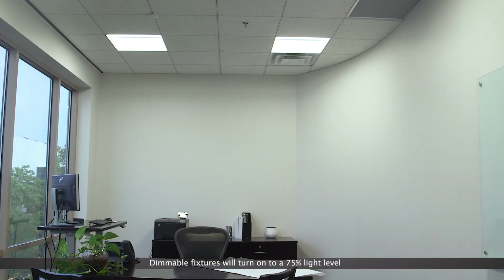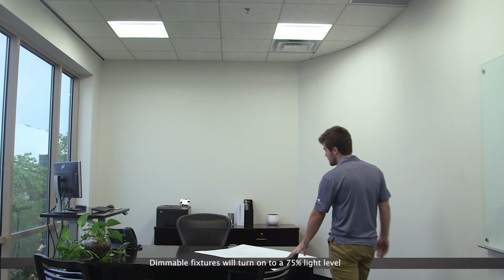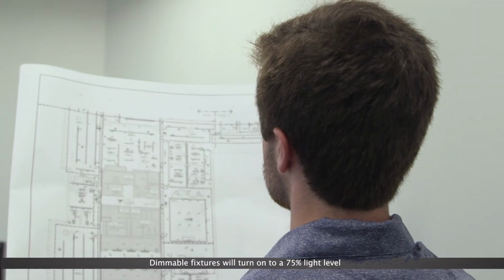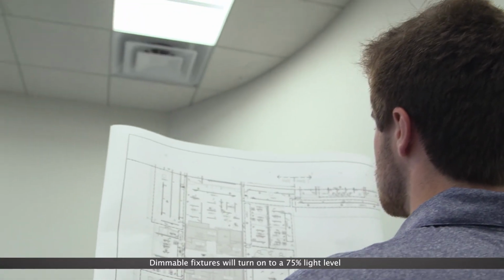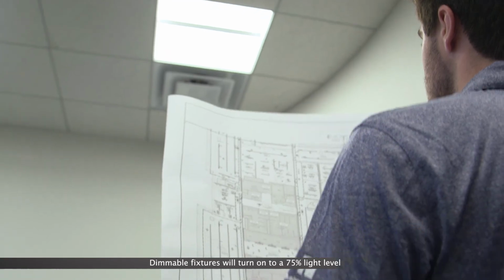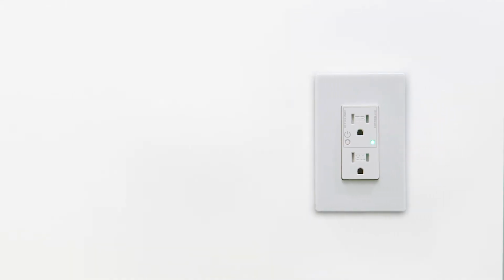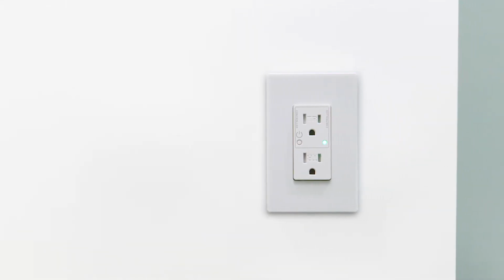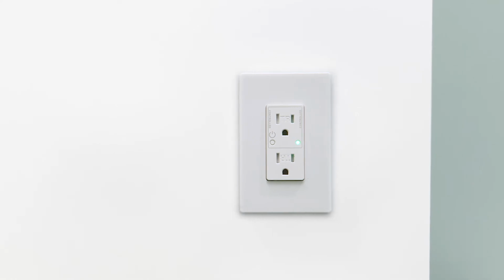Next, verify operation of WaveLinx relay switch packs. After power is applied, check that loads connected to relay switch packs turn on and remain on. Next, verify WaveLinx receptacles. After the connected circuit is powered, verify that the receptacle's green LED is illuminated.